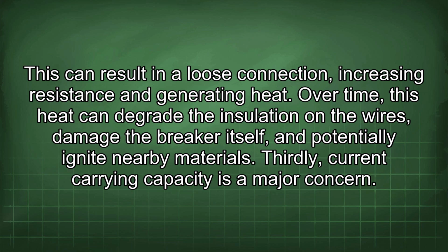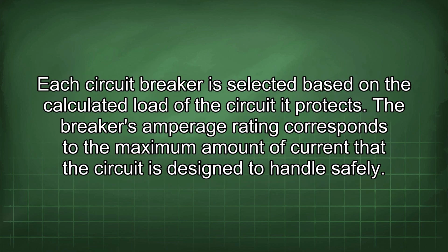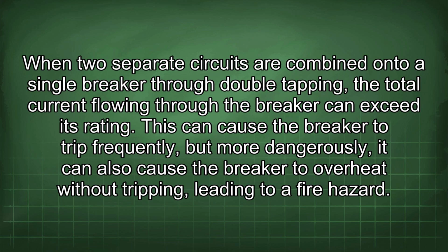Thirdly, current carrying capacity is a major concern. Each circuit breaker is selected based on the calculated load of the circuit it protects. The breaker's amperage rating corresponds to the maximum amount of current that the circuit is designed to handle safely. When two separate circuits are combined onto a single breaker through double tapping, the total current flowing through the breaker can exceed its rating. This can cause the breaker to trip frequently, but more dangerously, it can also cause the breaker to overheat without tripping, leading to a fire hazard.